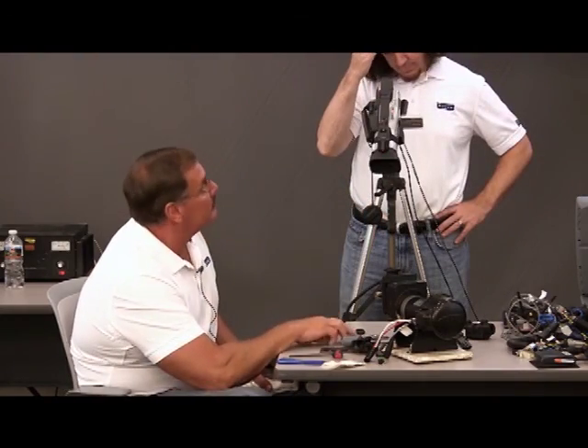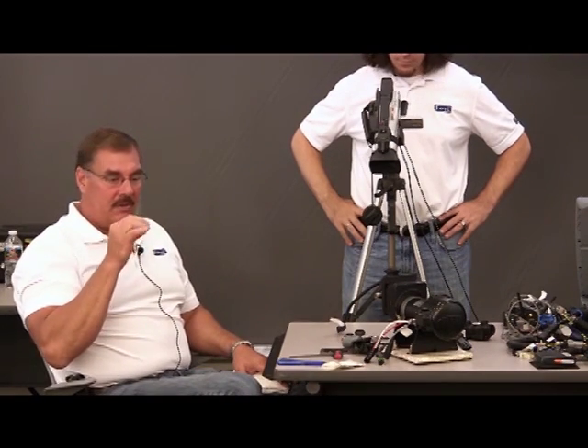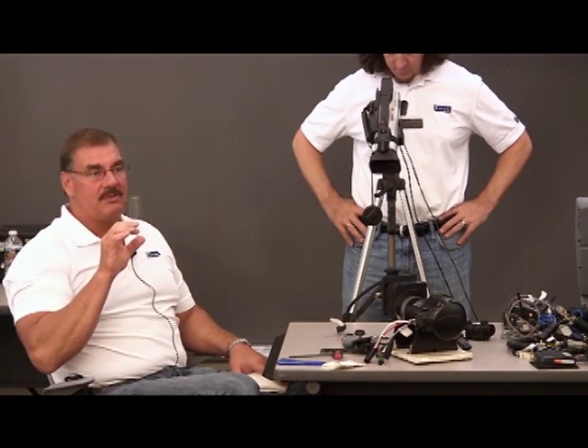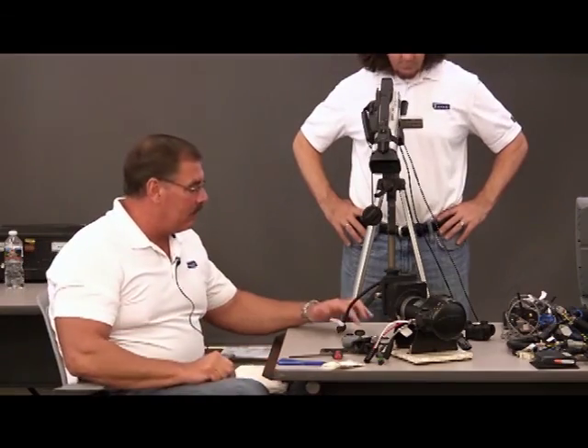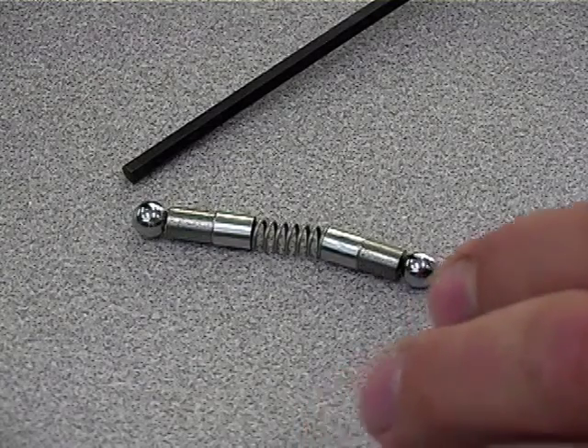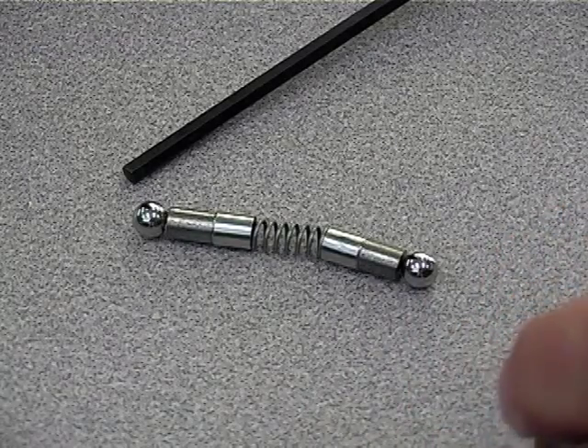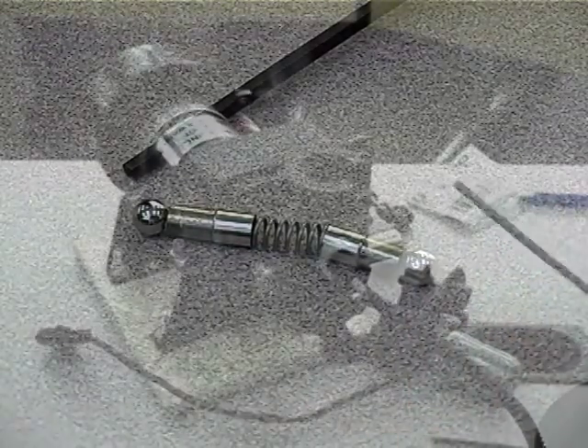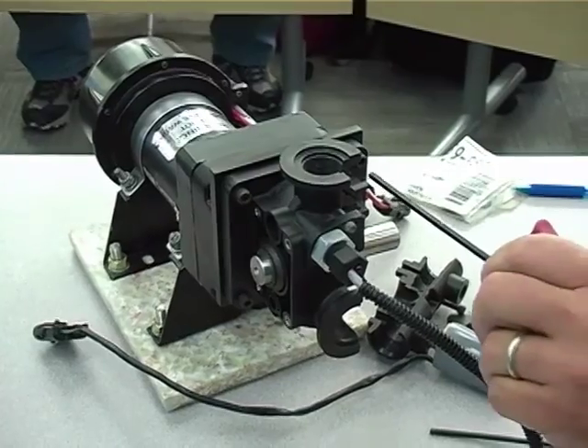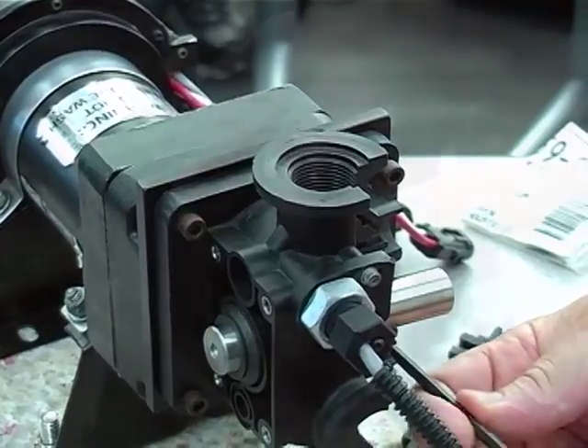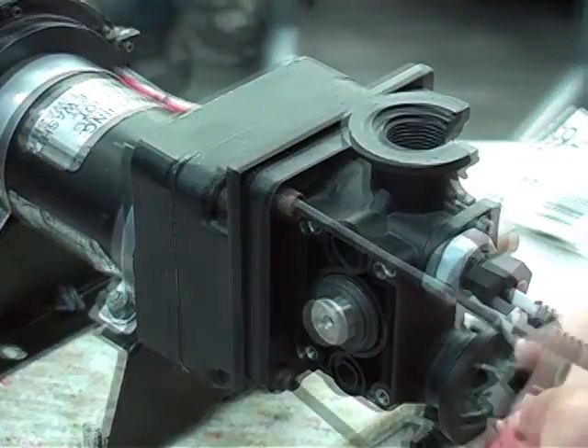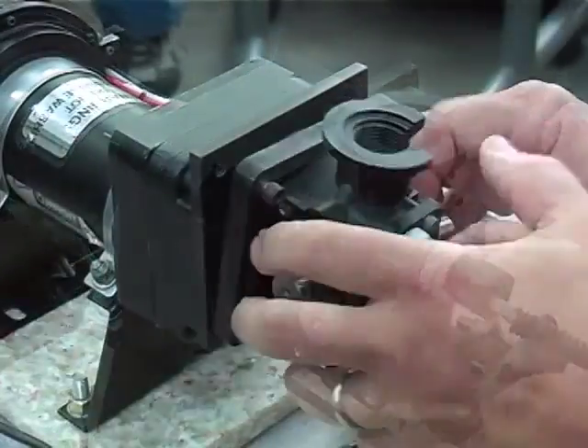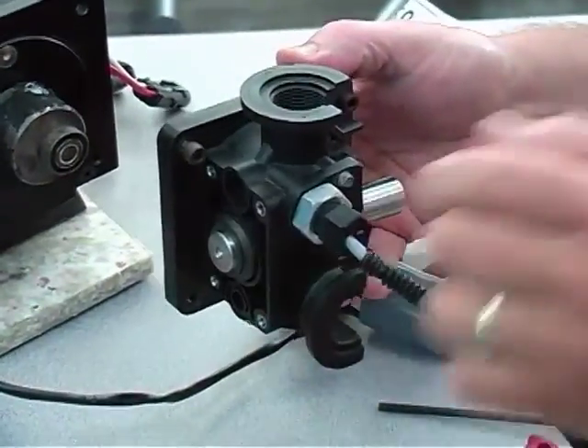The reason we did this, when it works in that channel, we found out when we're trying to calibrate a system at a very low rate with a real thin chemical substance, the water or whatever would actually pass by the balls as it goes through. So we found out that if we made them just a little larger, it catches it. Now I'm going to take the pump body off here. By the way, it's 5/32 for the pump heads, the left and the right, and 3/16 Allen wrench for this one.